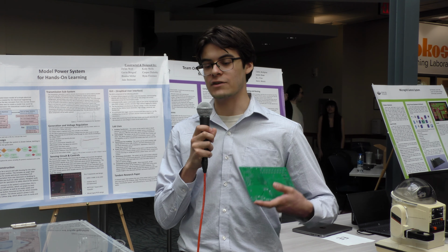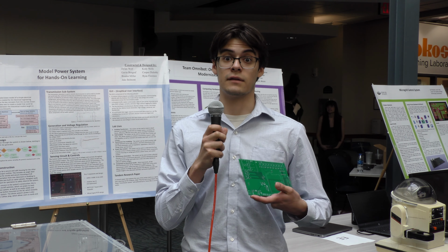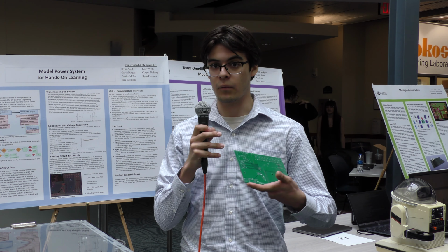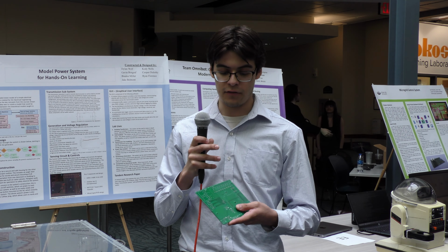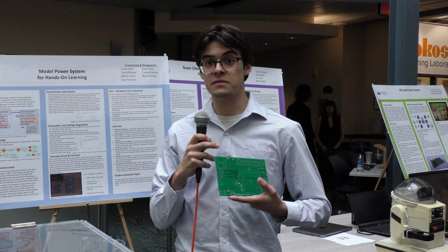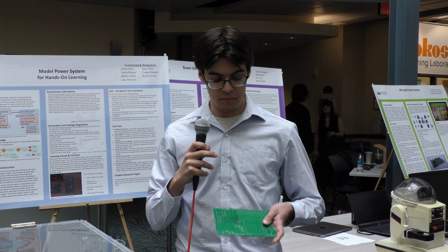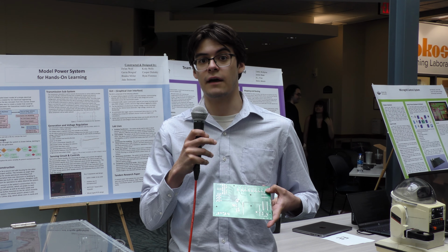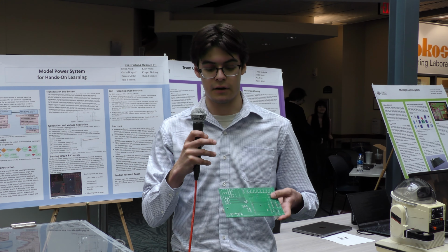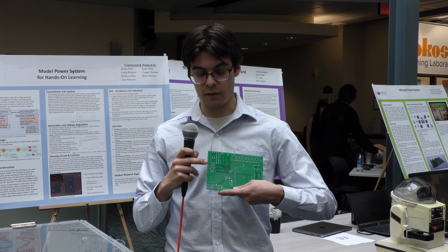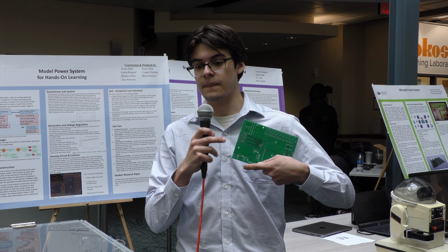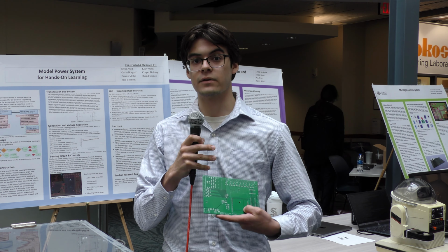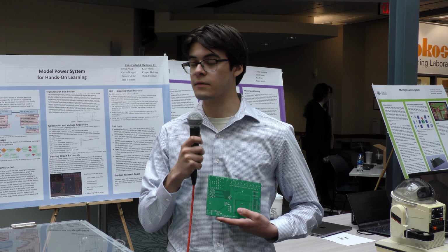That's how when we engage a fault, we see a current, and we see that it's higher than what we are expecting, and then we can act upon it, and what we do is we shut the contactors off. And so that's pretty much all there is to the control system. Over here we have the digital side, so this is where your contactors plug into, and this is how they receive their power or their signal to turn on and off. Right here is where our voltages and currents actually come from the system into our ADC. And then right here is where the microcontroller sits. And that's about all for the control system.